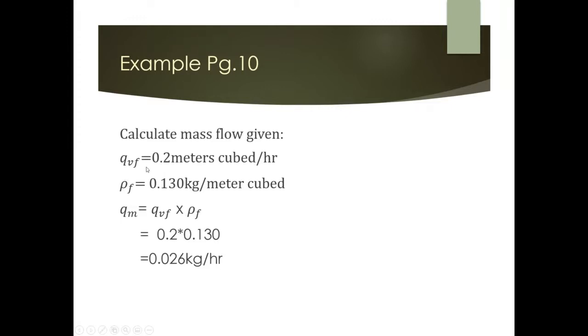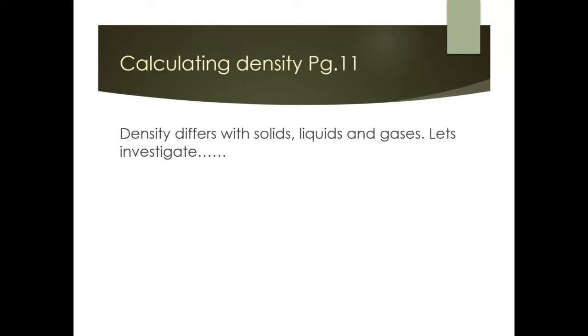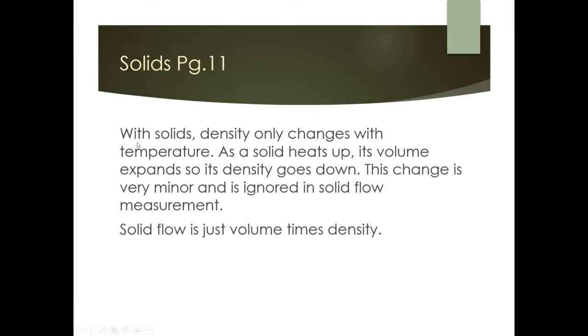Density is the key pivot point when distinguishing volumetric flow from mass flow. For solids, density only changes with temperature — as a solid heats up its volume expands and density goes down. This effect is very minor and is generally ignored in solid flow measurements, so solid flow is simply volume times density.